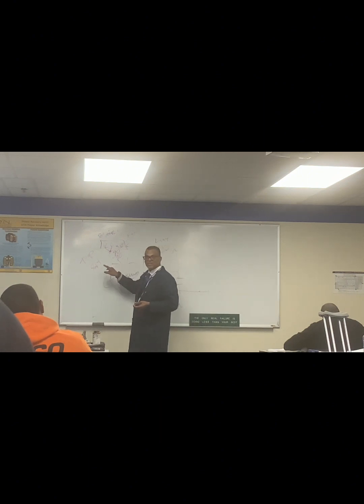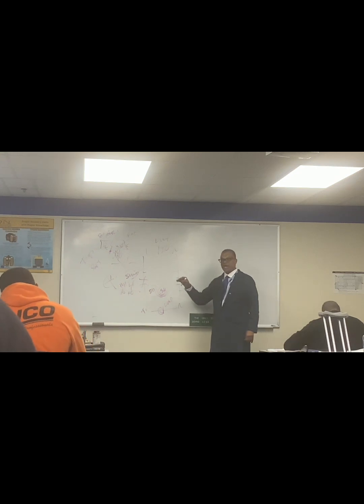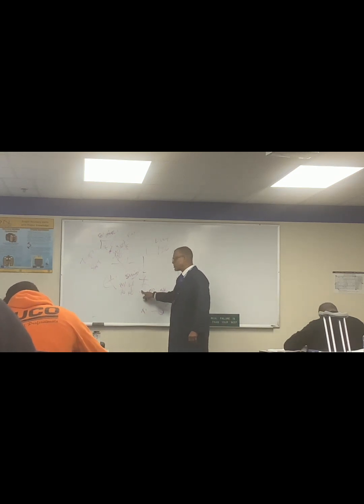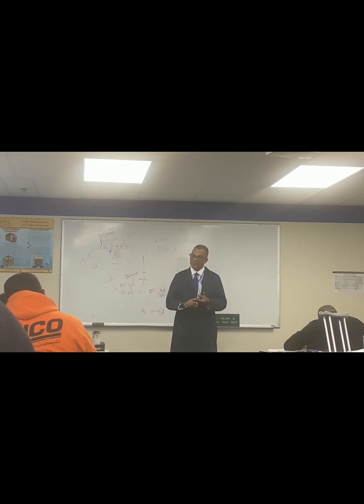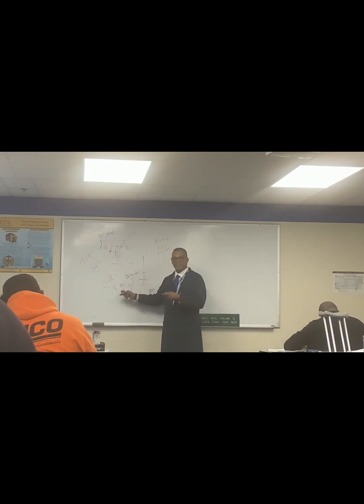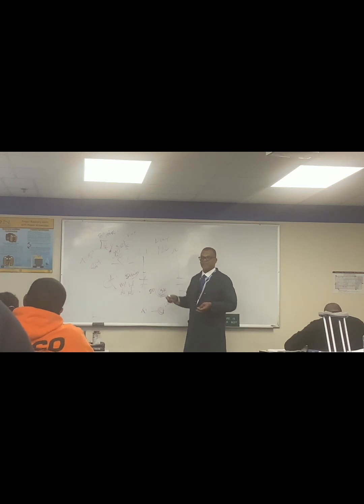So what does that look like inside of a thermostat? It opens. It's at operating temperature, no power to the contactor, the contactor opens. So it can be safety or operation. Operation means we met set point, nothing has failed in the series circuit. It's perfect. But we have reached our satisfaction at the thermostat, and now we cycle off. So it's operating and safety.